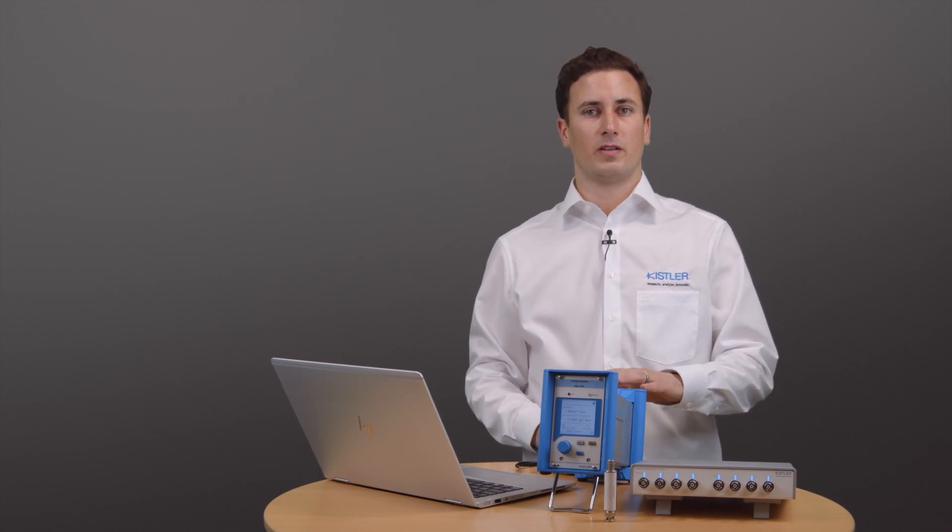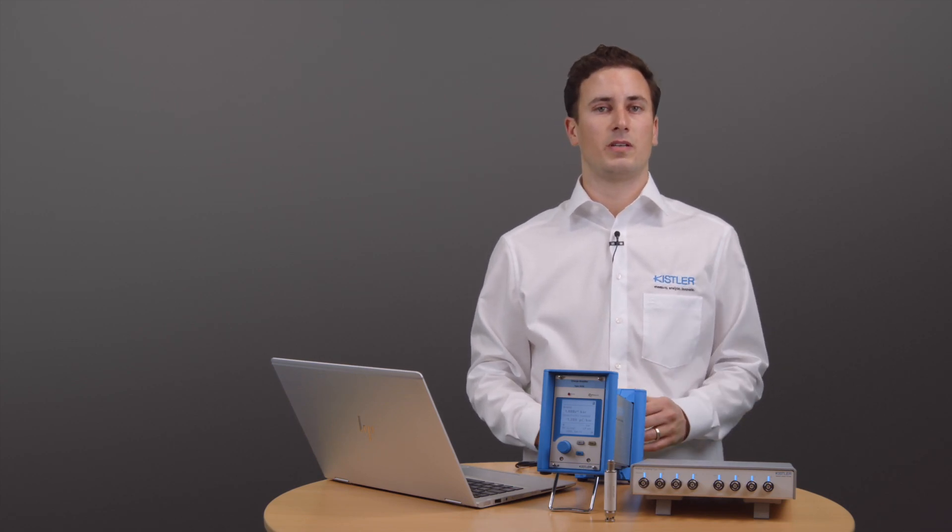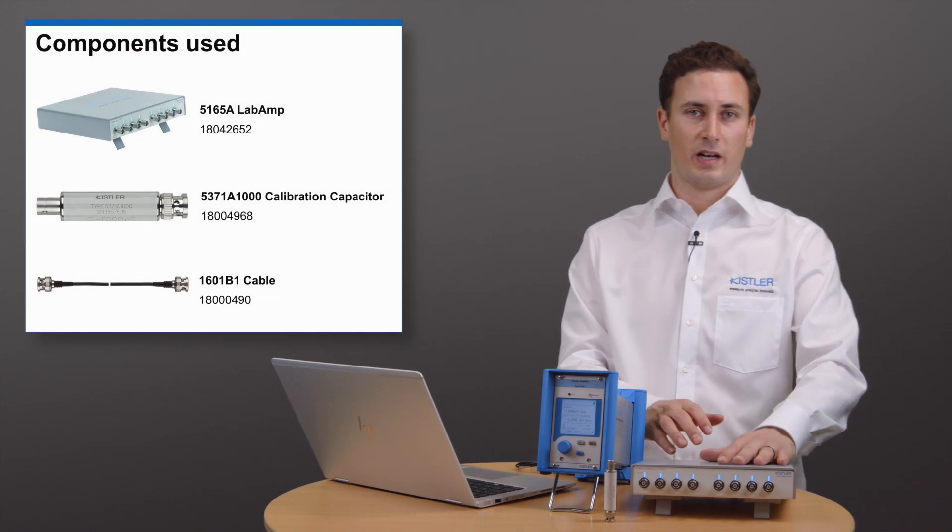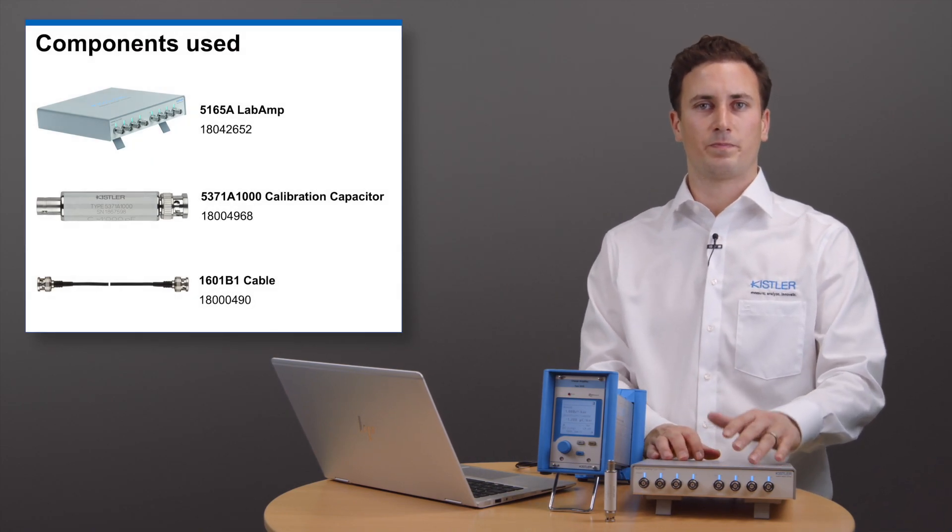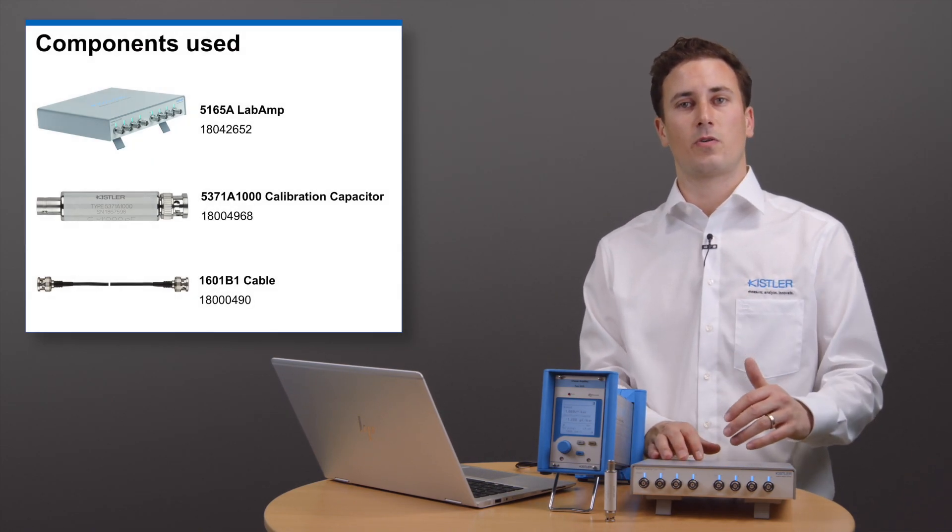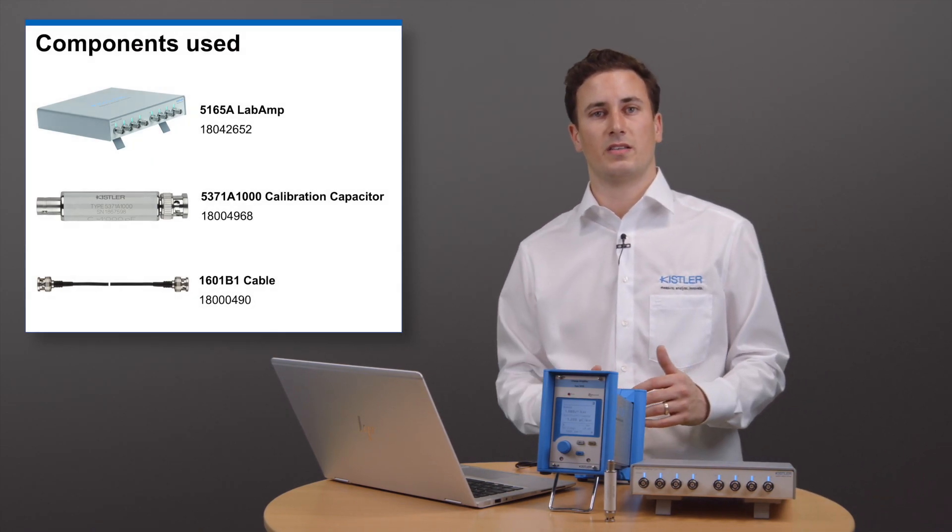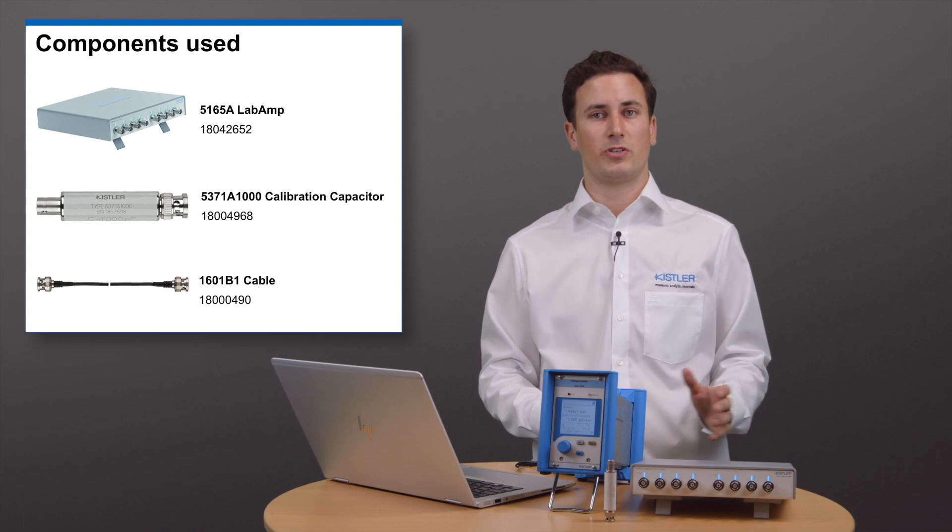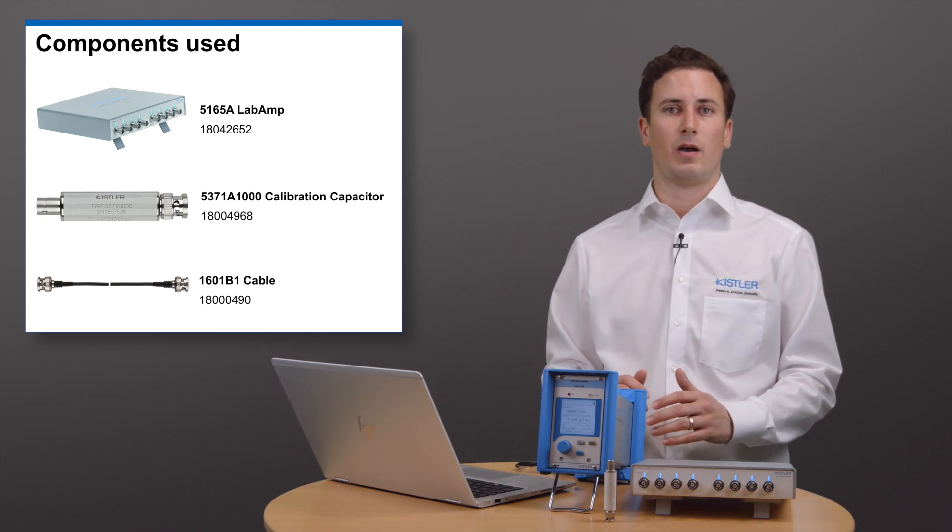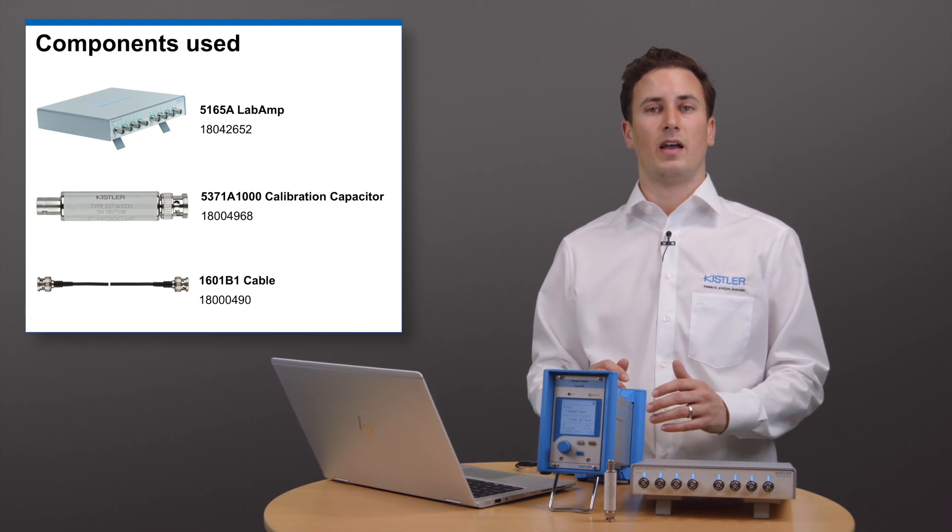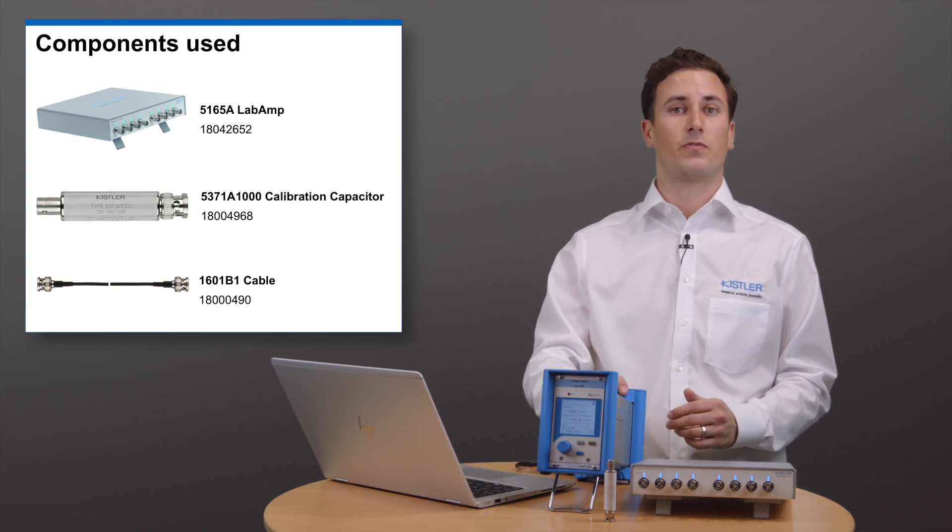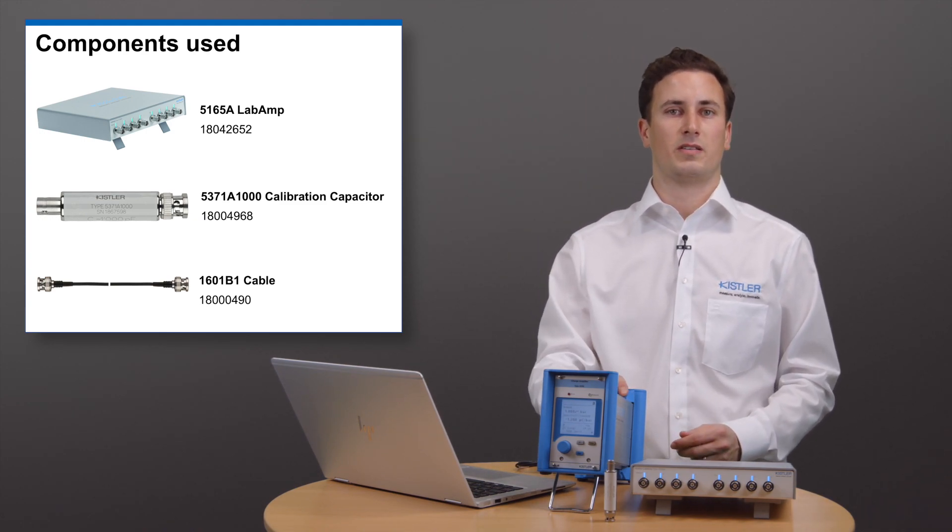Apart from our unit under test, we will need the following components. A dynamic lab amp, as this will be the core of our test setup. This device allows us to generate analog output signals as well as to measure the voltage from our unit under test.